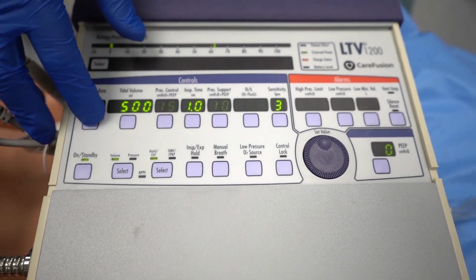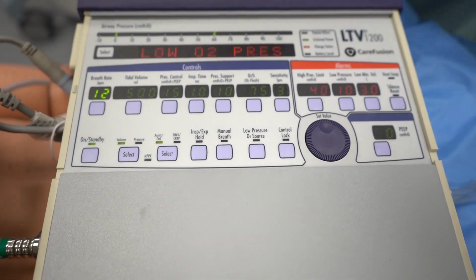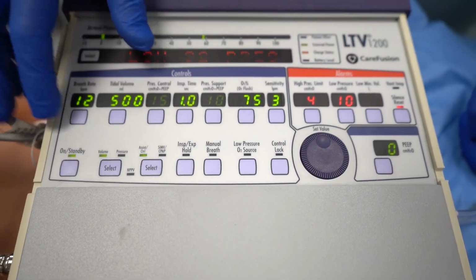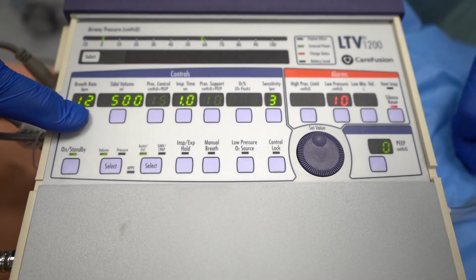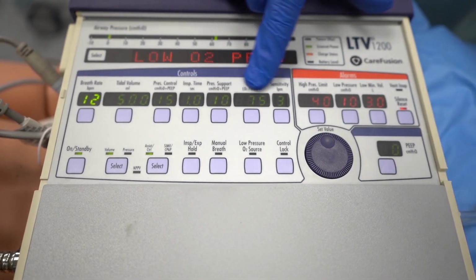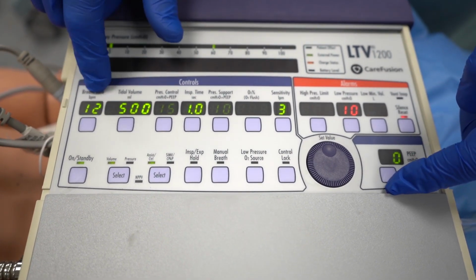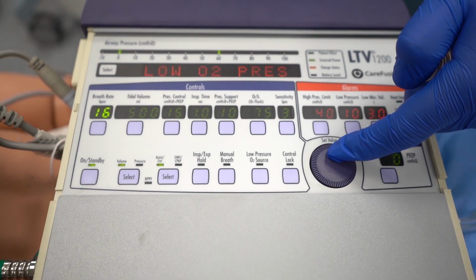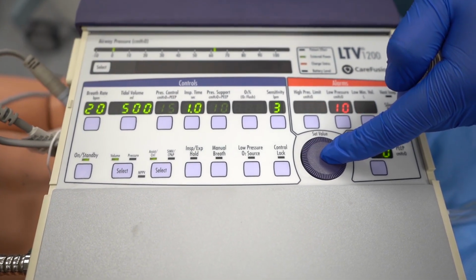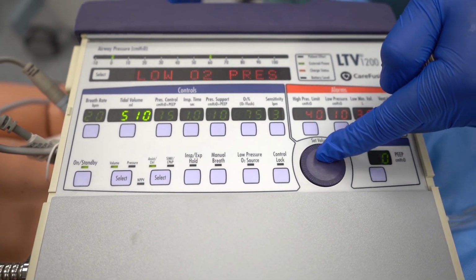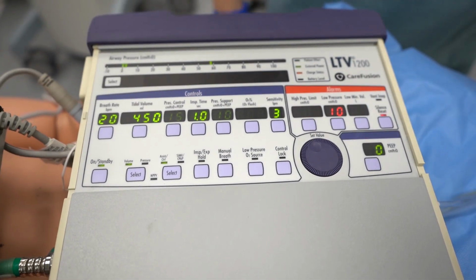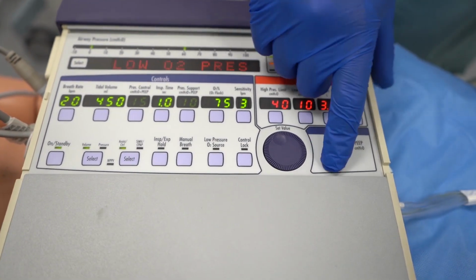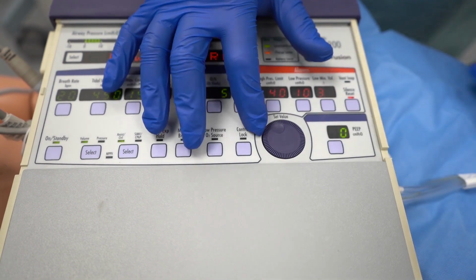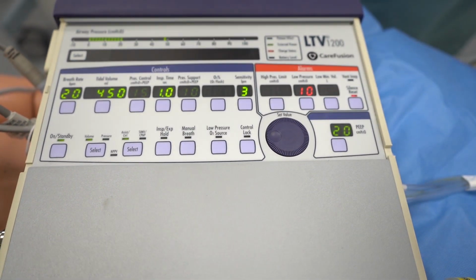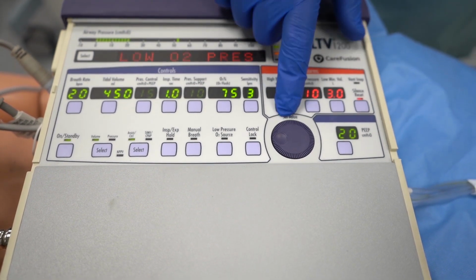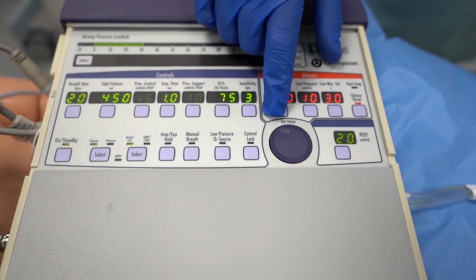Right now we're on volume control, so you can change your rate and your tidal volume by simply selecting the button underneath. You'll notice that everything else gets faded out, so for right now, your rate is the only thing that's selected. You can use the dial to change it and then lock it in. Same thing with the tidal volume: dial, change it, and lock it in. Your PEEP is located down here. On the LTV, you can go up to 20 of PEEP. And your alarms are located in the red box here, so you can set your alarms here.